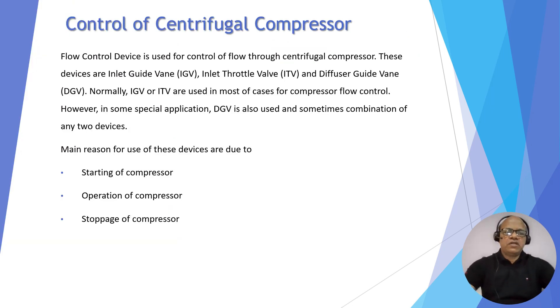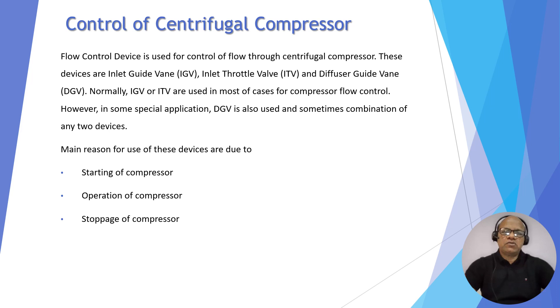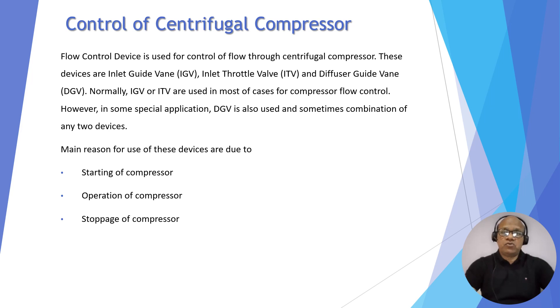First of all, let's understand why devices are used for the control of the centrifugal compressor. The flow control devices used for control of the compressor operations are inlet guide vane (IGV), inlet throttle valve (ITV), and diffuser guide vane (DGV). Normally IGV and ITV are used for most cases of compressor control. However, in some special cases DGV is also used, or sometimes a combination of any two devices.